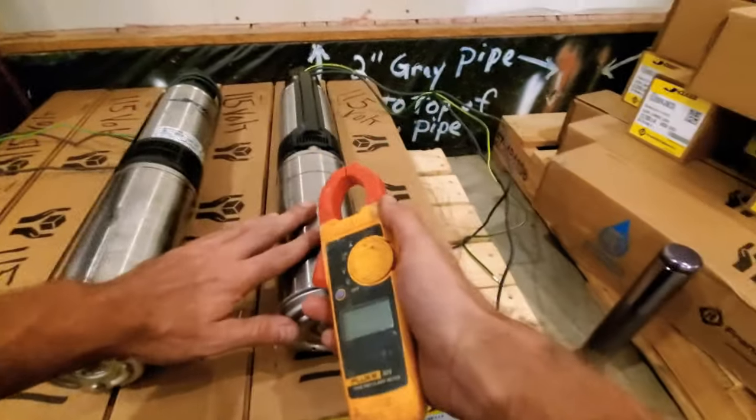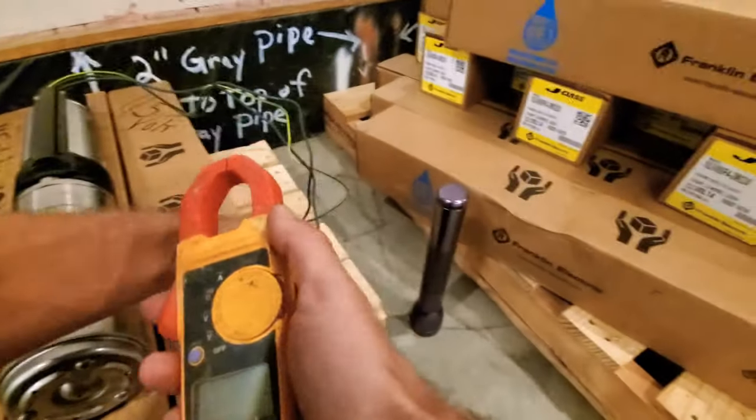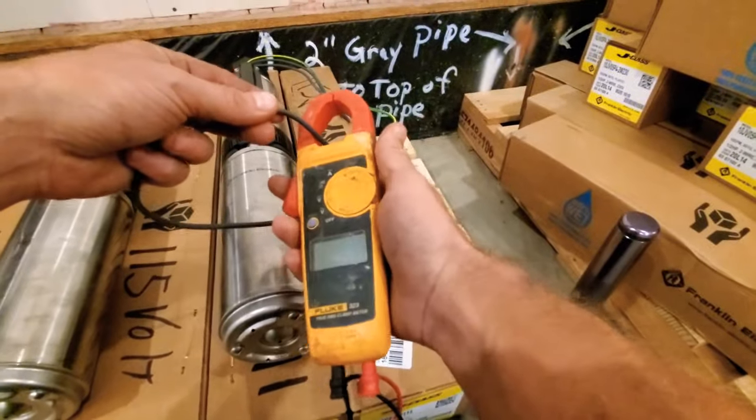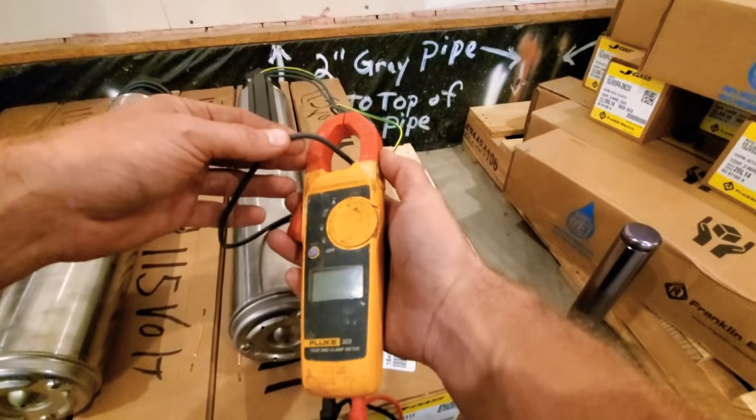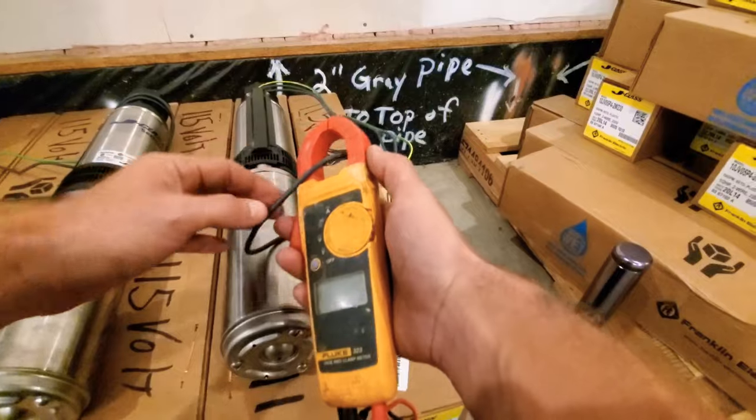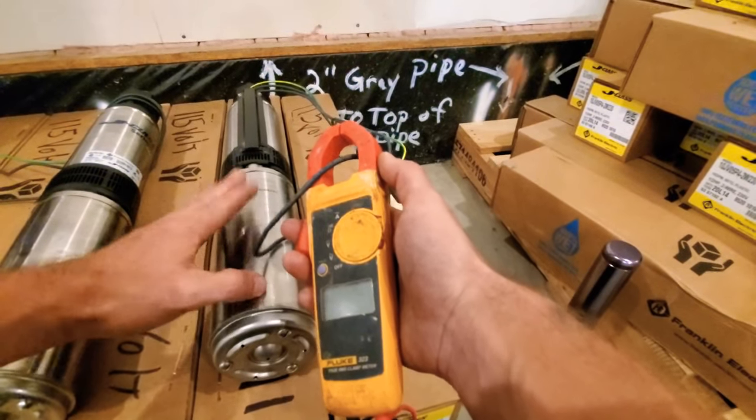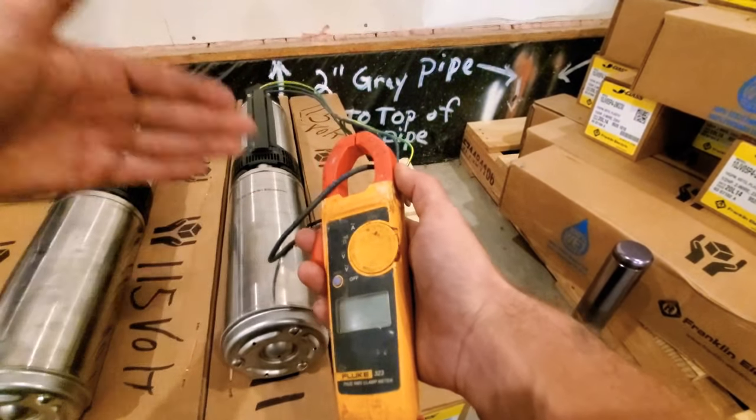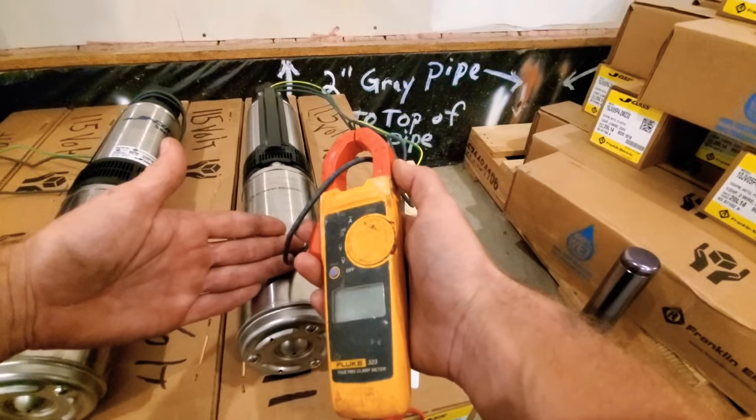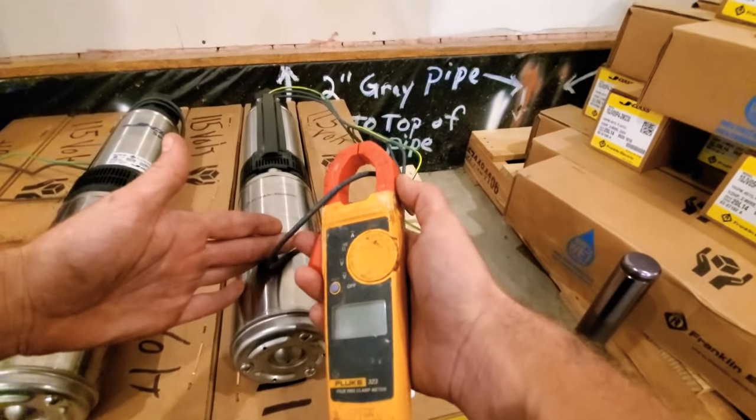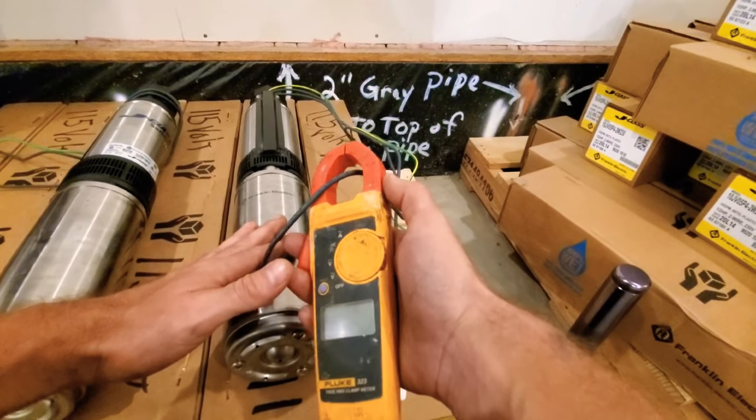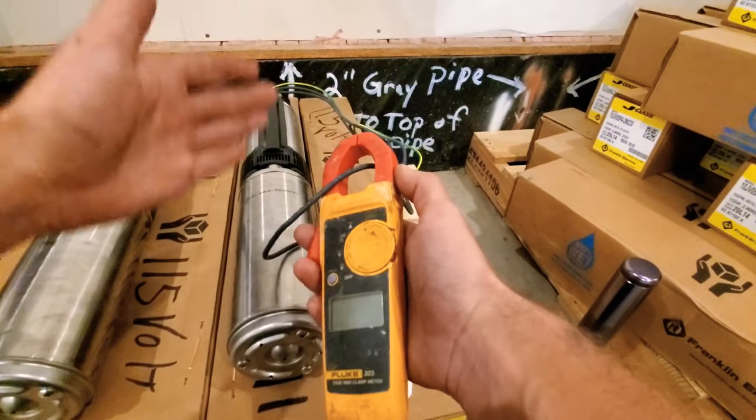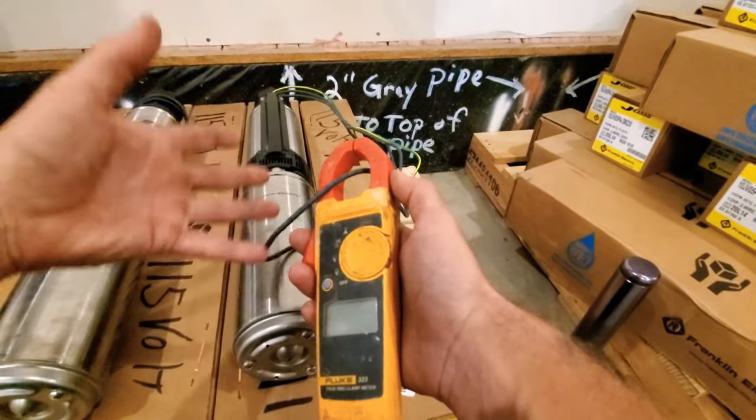If you come over here to the 240 volt well pump and you clamp it around one of the wires, you should read somewhere around six to six and a half, maybe seven amps, all depends on whatever manufacturer made that motor. A half horsepower is going to pull six amps, three quarters going to pull closer to seven, and a one horsepower is going to pull closer to nine.